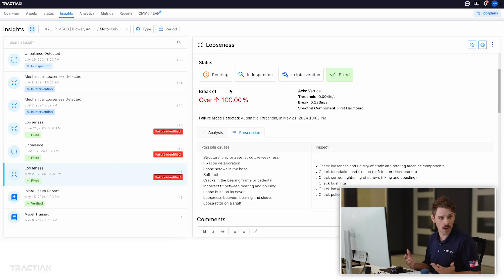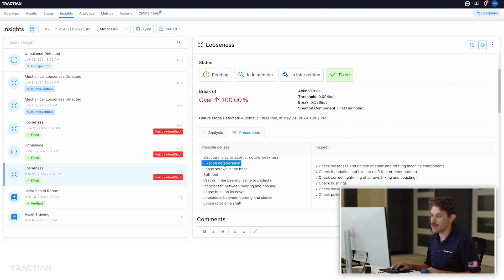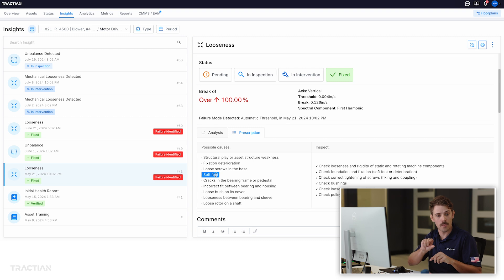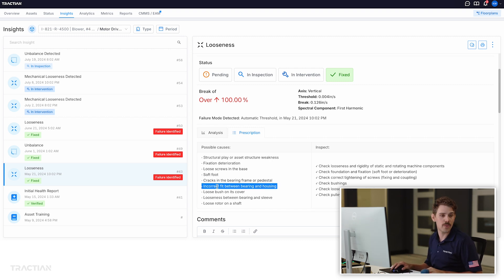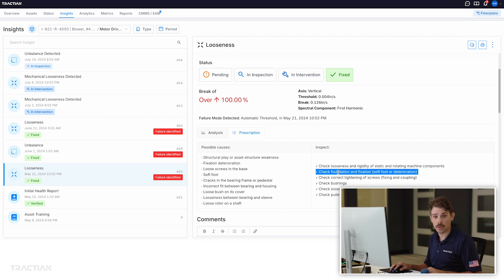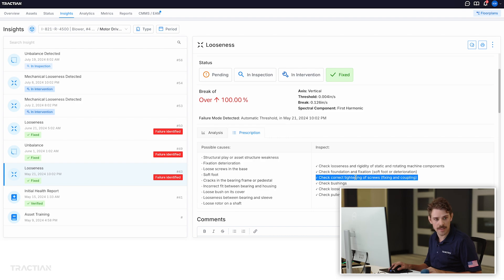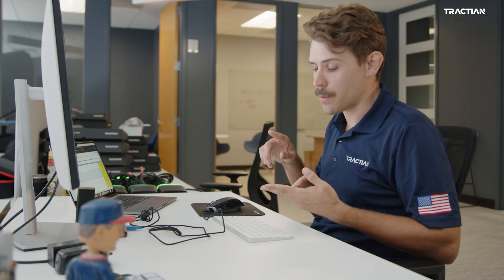Some possible causes for mechanical looseness are potential deterioration of the base, loose screws in the base, potential soft foot in the motor where the foot is starting to bend, cracks in the bearing frame, or an incorrect fit between the bearing and the housing or shaft. From an inspection perspective, we would check the foundation itself, check the looseness of an asset, check any bushings, or any kind of tightening or fixation — be it the coupling, the motor bolts, the pump base bolts — really anything keeping that asset secured to its base.